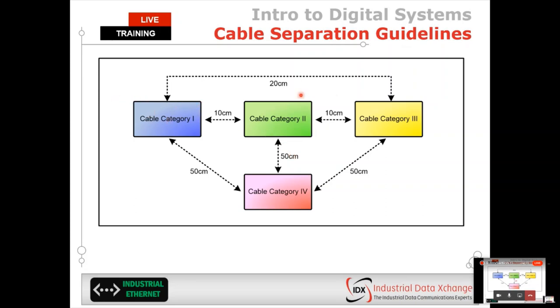Cable categories: we separate cables into different categories based on their voltage and function. Cable category one would be your standard 24 volt DC power supplies, your industrial Ethernet cables, your PROFIBUS cables—pretty much anything below 60 volts DC and 25 volts AC falls into cable category one. Any of these category cables can sit right next to each other; there's no need to separate them at all.